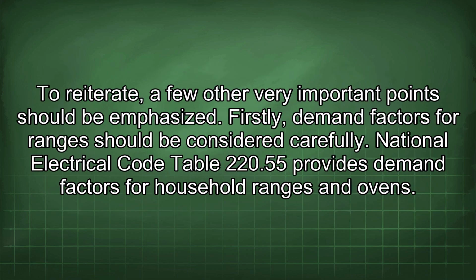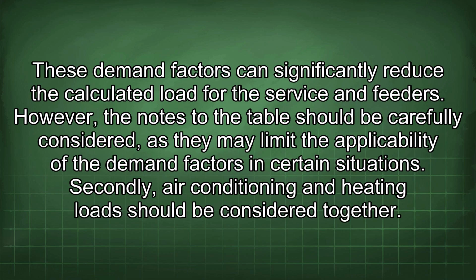To reiterate, a few other very important points should be emphasized. Firstly, demand factors for ranges should be considered carefully. National Electrical Code Table 220.55 provides demand factors for household ranges and ovens. These demand factors can significantly reduce the calculated load for the service and feeders.